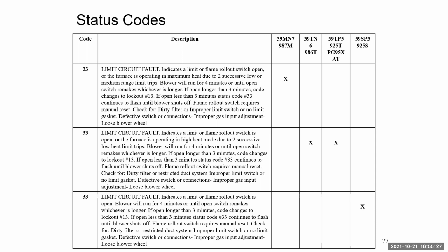So they figured if they open the faulted zone 100%, open everything else 25%, your customer's going to start sweating and wonder why. And then they're going to call and say, hey, my stuff's not working right. And you're going to get out there. Again, it's a new fault code. You will not find it in a manual anywhere. So if you find 126 on your thermostat, don't even go to a manual, because you're going to sit there and look forever. You will not find it. As of now, updated thermostats down the road, it might be there, but as of now, you will not find it in manuals. So yeah, it's 126, and it is referring to limit trips on your system.